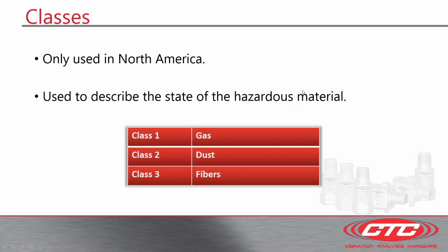Classes are only used in North America, and it's CSA's way to describe the state of hazardous material. Class 1 is a gas, Class 2 is a dust, and Class 3 is a fiber.